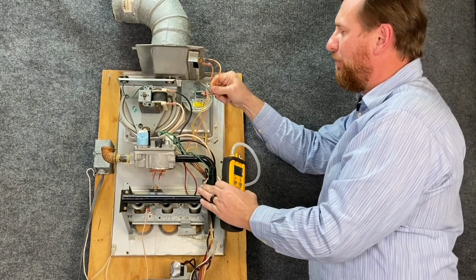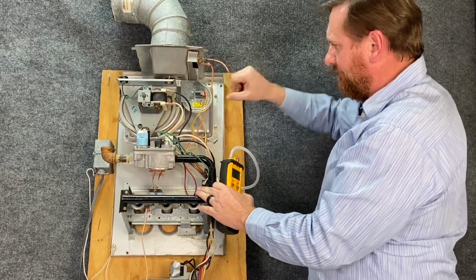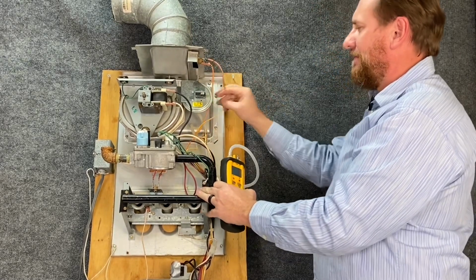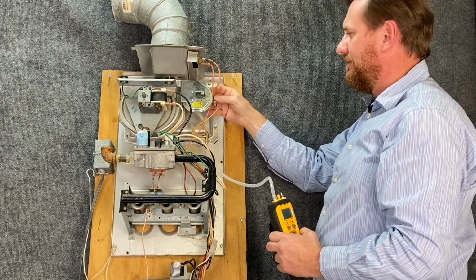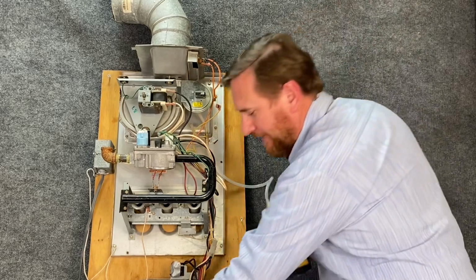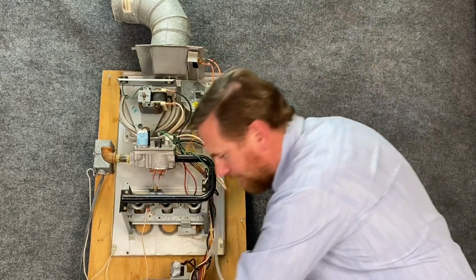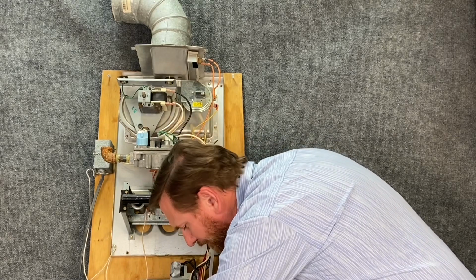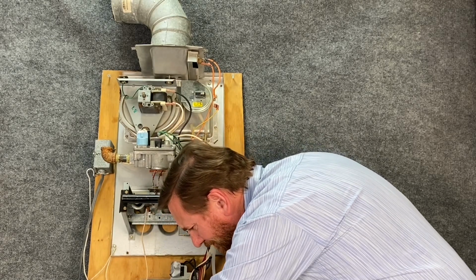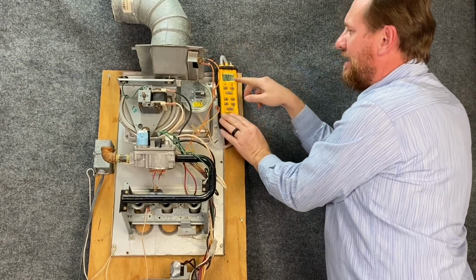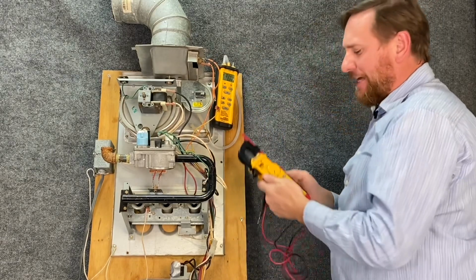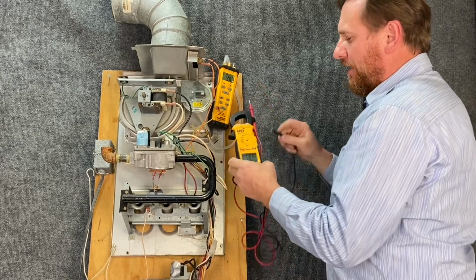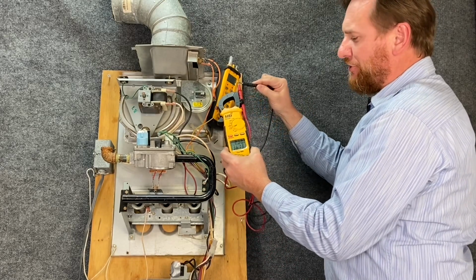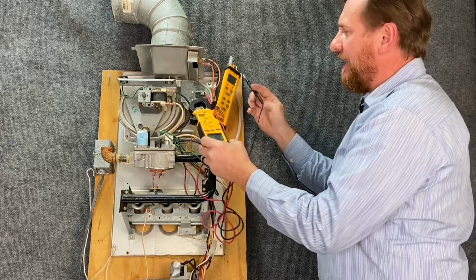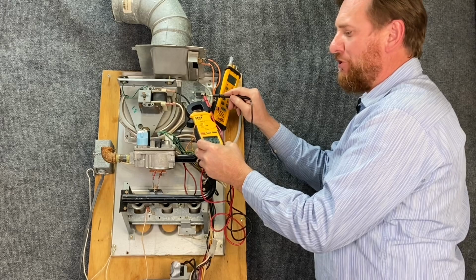What we can do is we can pull these wires loose. And I can have a call for heat. And with my manometer, I know I'm pulling the proper vacuum. I can then take my meter and turn it to ohms. OL, infinite resistance, open. And if I touch the terminals together, I got 0 resistance, closed. If I check across the switch, I'm showing 0 ohms of resistance.